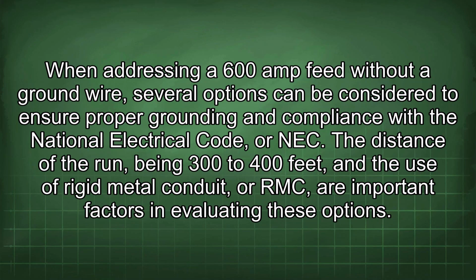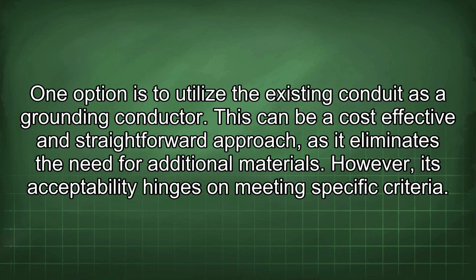When addressing a 600 amp feed without a ground wire, several options can be considered to ensure proper grounding and compliance with the National Electrical Code, or NEC. The distance of the run, being 300 to 400 feet, and the use of rigid metal conduit, or RMC, are important factors in evaluating these options. One option is to utilize the existing conduit as a grounding conductor.